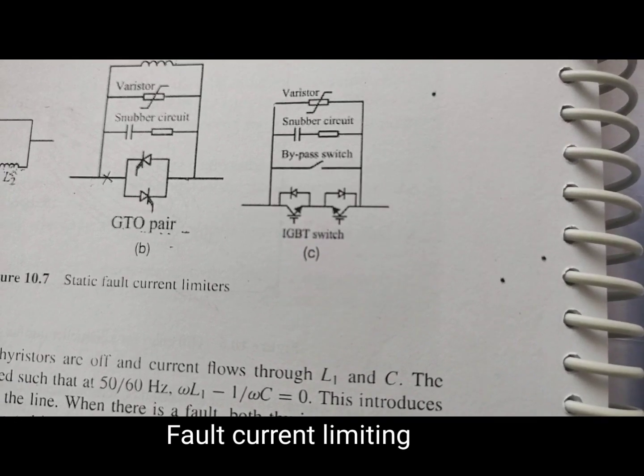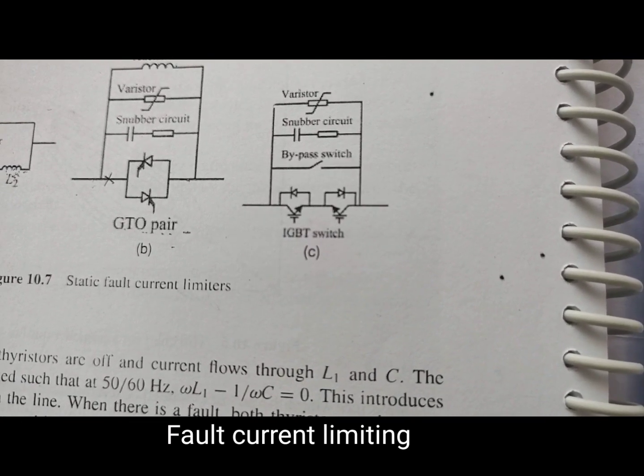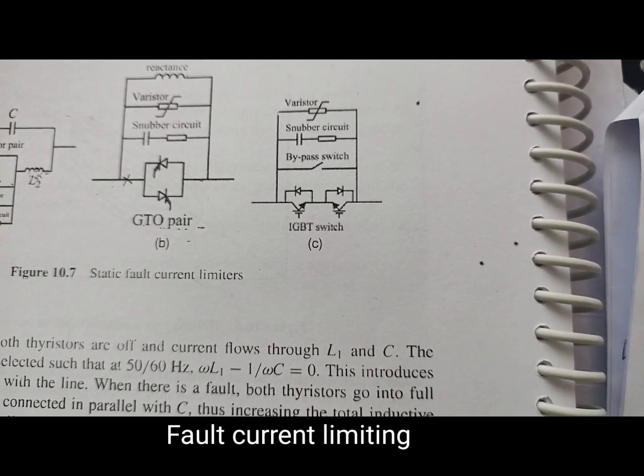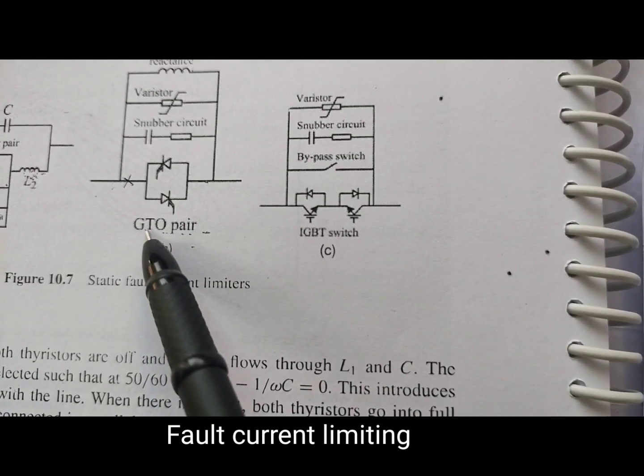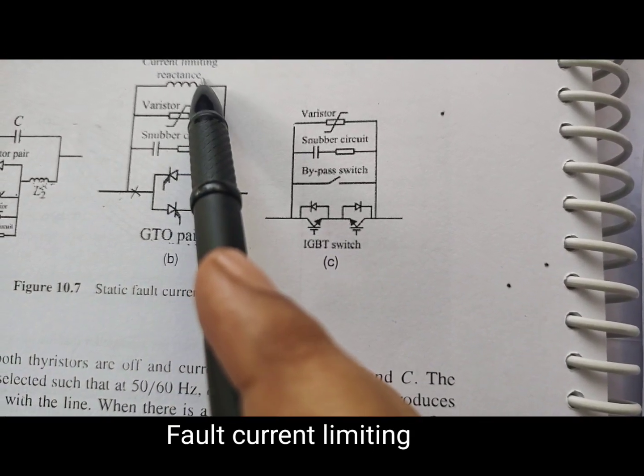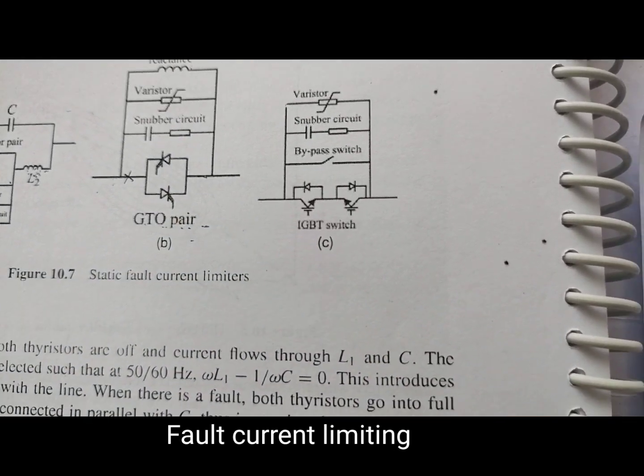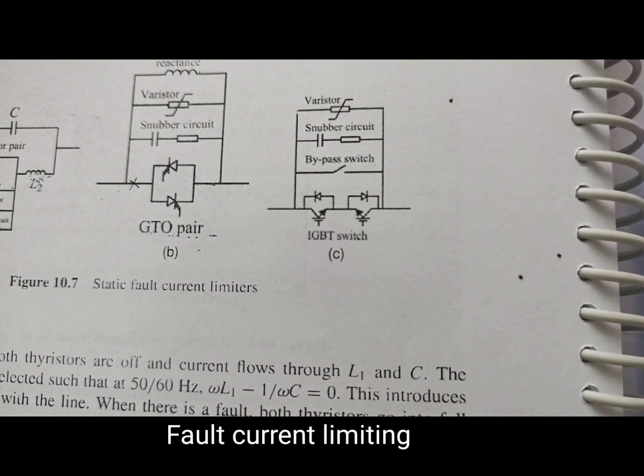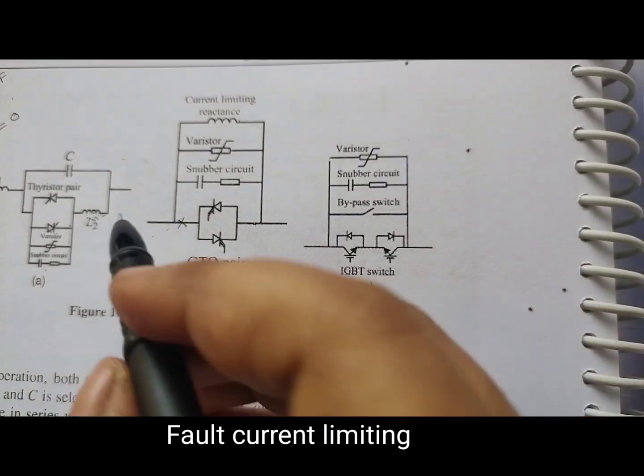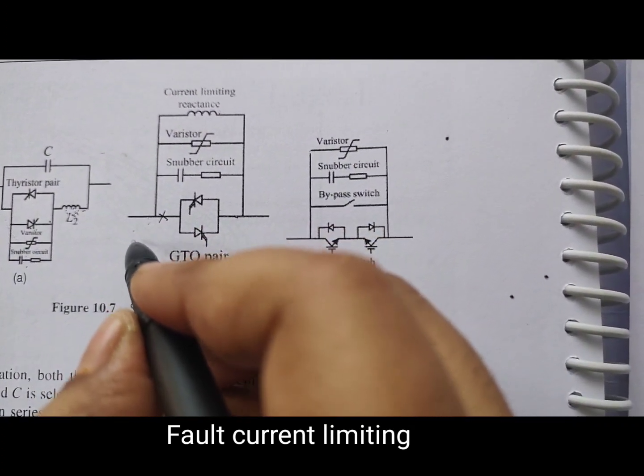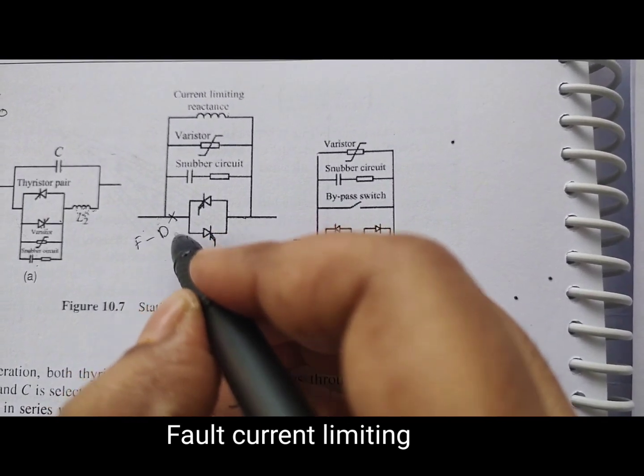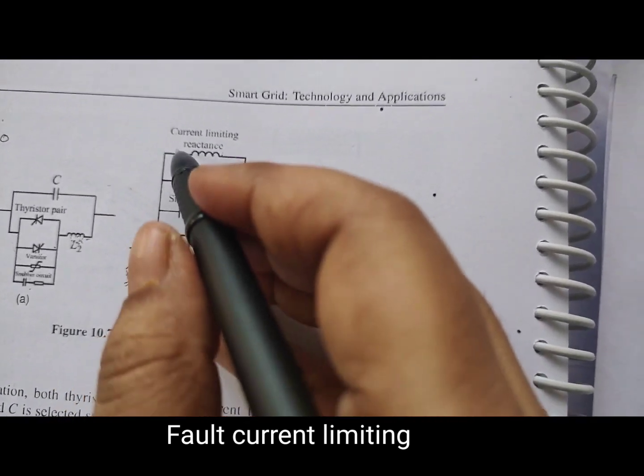It is possible to continuously switch the GTO switches on and off so that the fault current is shared between the GTO and the parallel limiting reactance. This is about figure 2. Remember, during a fault condition the current is diverted and goes through the current limiting reactance.